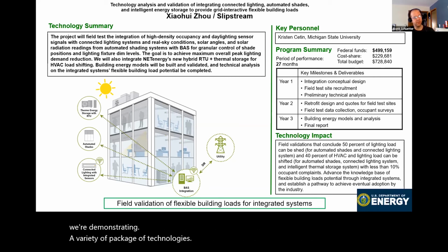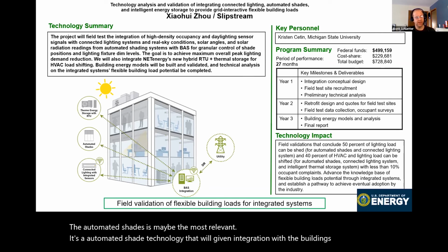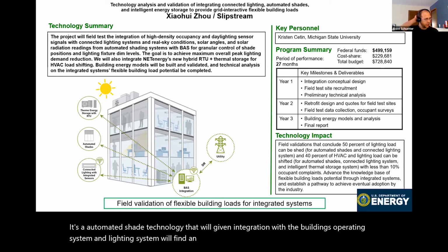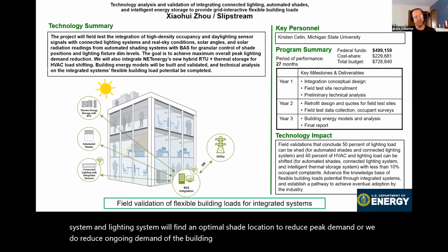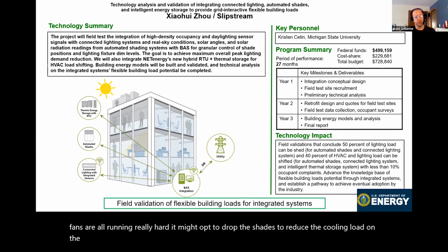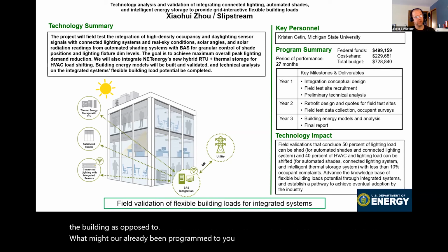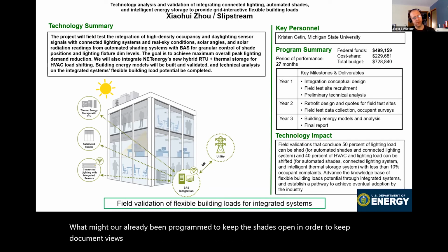The automated shades are maybe the most relevant. It's an automated shade technology that, given integration with the building's operating system and lighting system, will find an optimal shade location to reduce peak demand or ongoing demand of the building. So if it's hot outside and the compressors and fans are all running hard, it might opt to drop the shades to reduce the cooling load, as opposed to what might already have been programmed to keep the shades open for occupant views or to maximize savings.